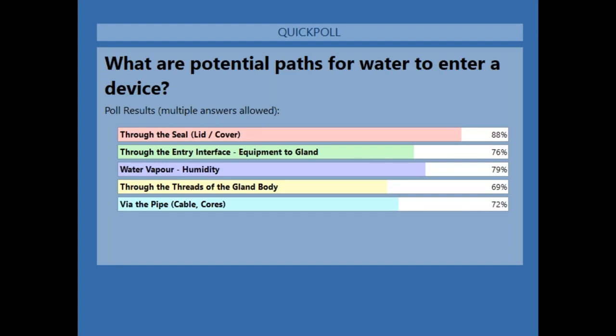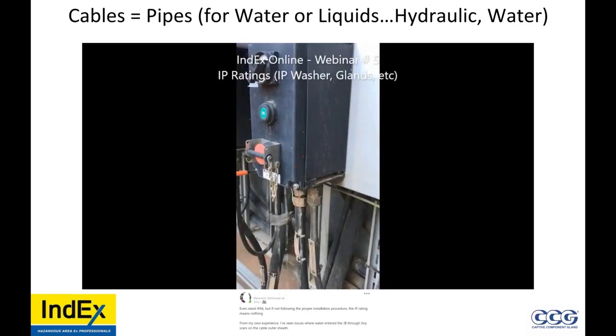Also, in this video, where the water came from was up the cable. Other people have found this out. At the bottom here, a gentleman said that even with IP66, if it is not followed properly, the IP means nothing. But also he said, from my own experience, I've seen water enter the JB through tiny cuts in the outer sheath of the cable. Piping of water up a cable. Different temperature, height, and pressure will make things flow up a cable.